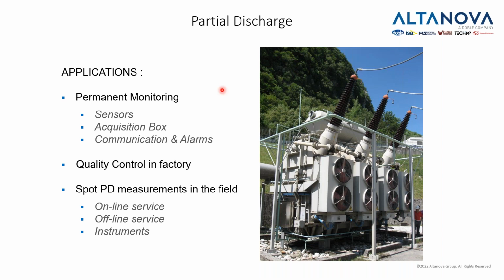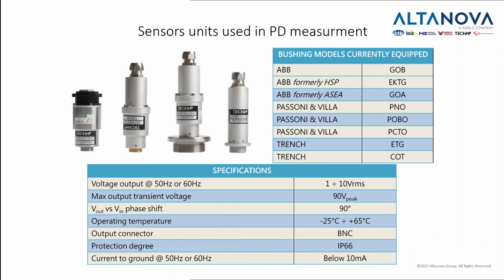We can also do a permanent monitoring of the transformer, which is often done if that transformer is important for us. Which sensors do we use and when do we place them? Well, this is one of the sensors. It's called a tap adapter, and it's not bigger than your palm. It's effectively a capacitive coupler. There are different types because they will be put into the tap adapter, which we mentioned before, the one which we used for tan delta or power factor measurement. While these are the acquisition units, which we will use to measure the tan delta and the partial discharge.